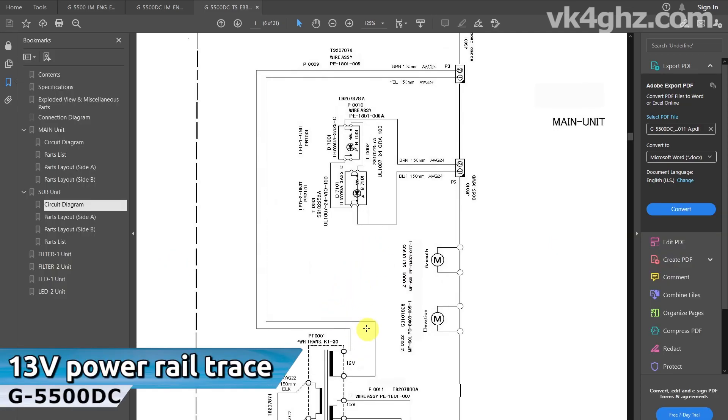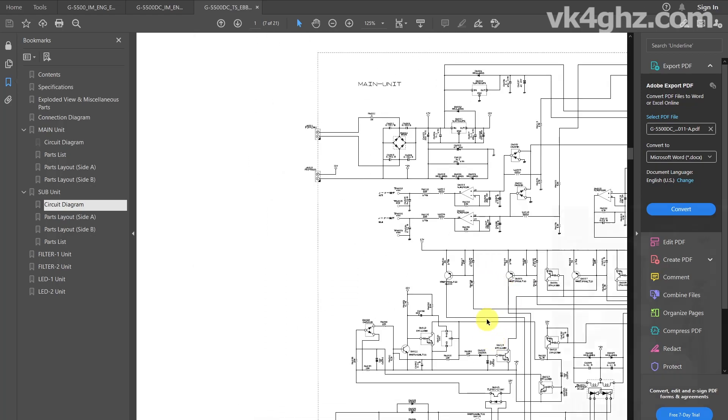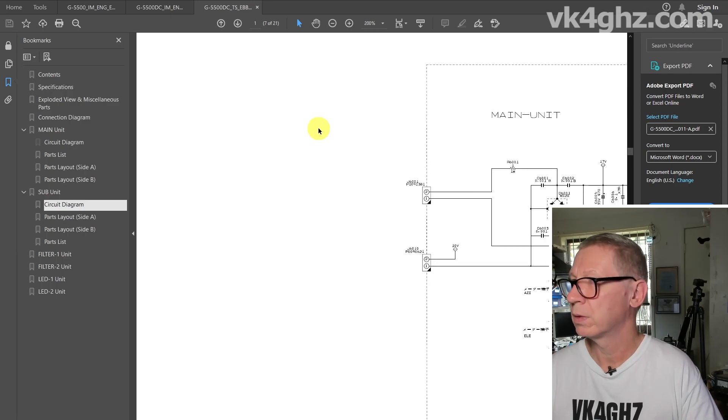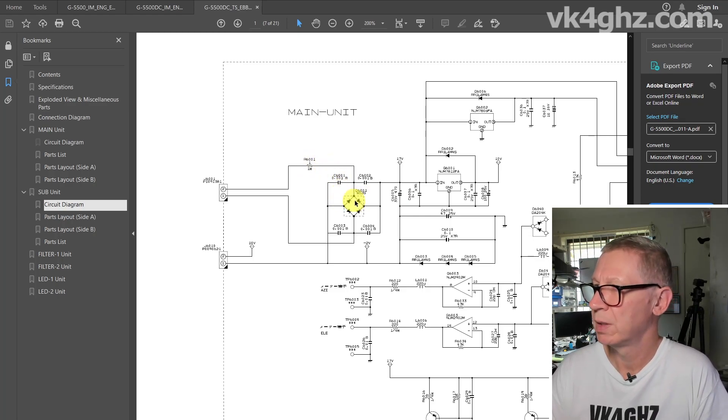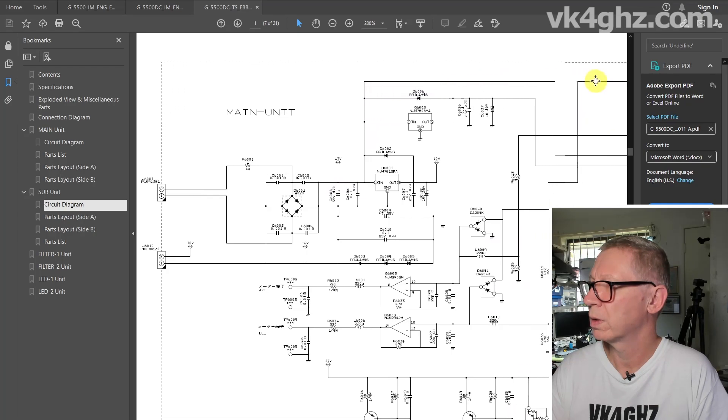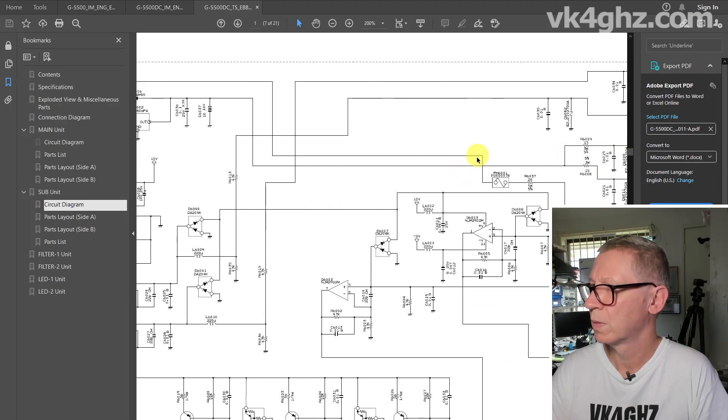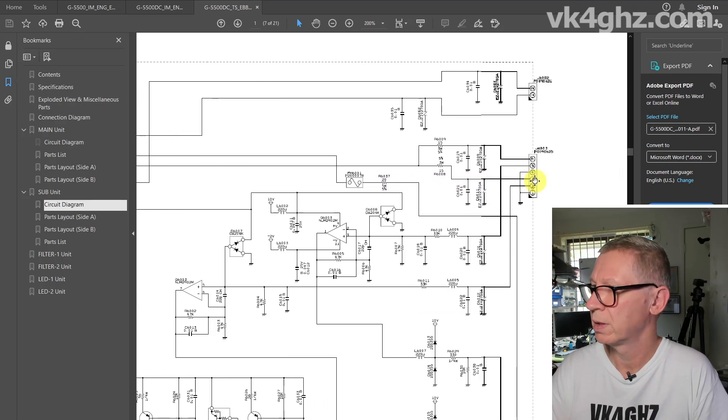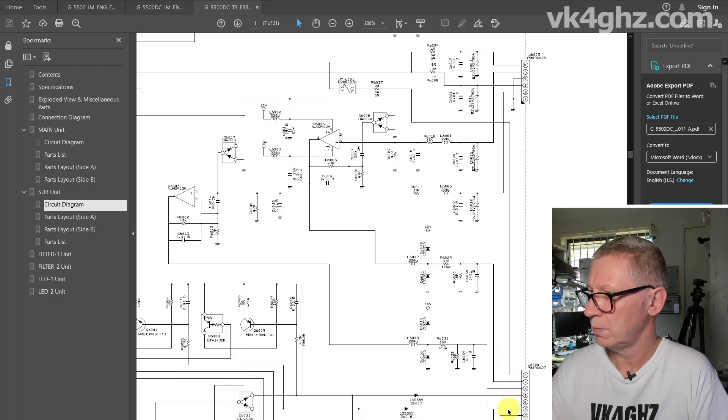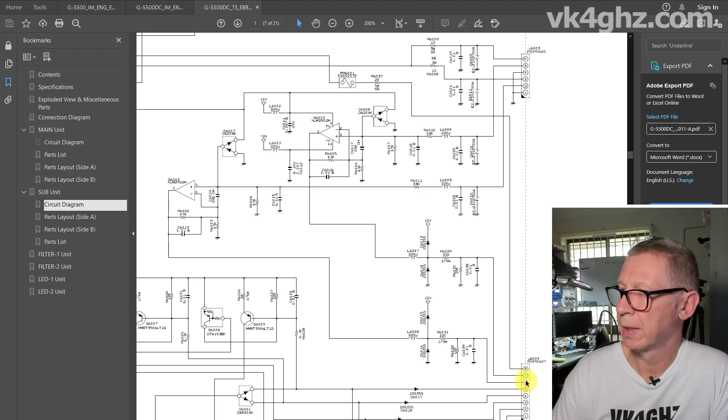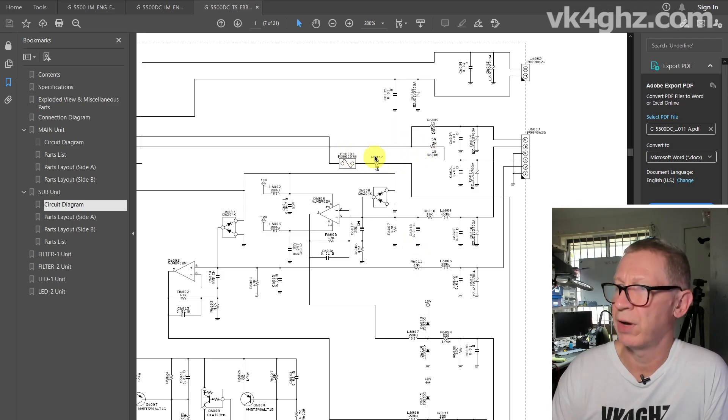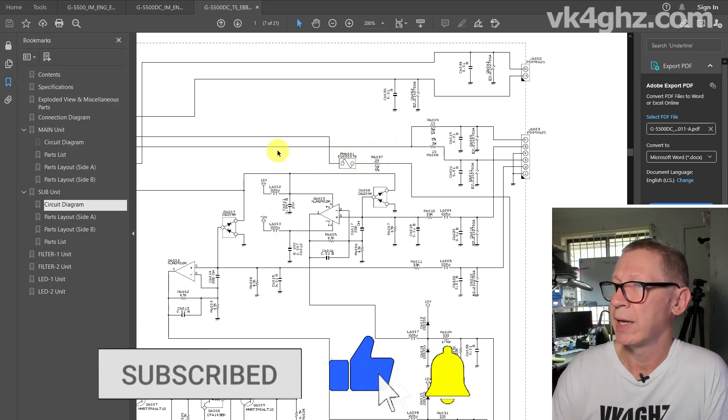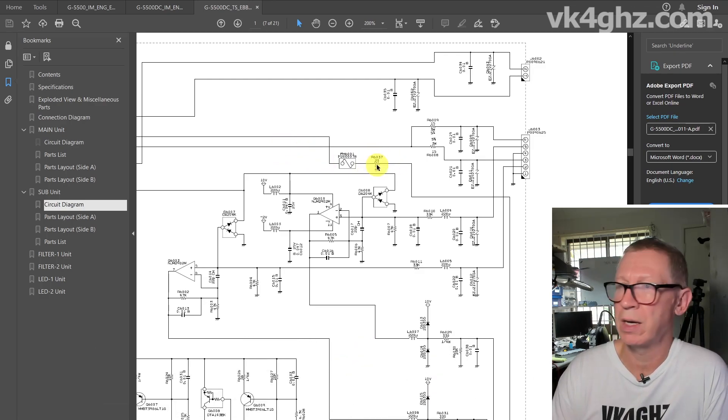Looking at the schematic of the G5500 DC, we've got a 12 volt secondary on the AC transformer. It goes into J6001 through a 1 ohm 1 watt resistor to our bridge rectifier. It goes through a fuse, through the 20 ohm 5 watt resistor down to the external control connector. So the only thing new about the G5500 DC is that it's got a fuse in line, and that 1 ohm resistor, but it's essentially the same.